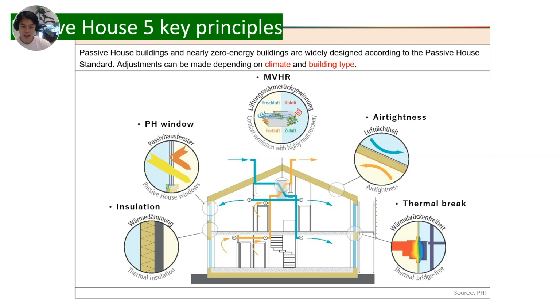That's why mechanical ventilation systems incorporate heat recovery features, namely HRV, heat recovery ventilation, and ERV, energy recovery ventilation. In high humidity environments, ERV systems are necessary because they regulate humidity, providing a form of passive dehumidification. Note that this is not the same as a conventional dehumidifier. However, in extremely humid conditions, a dehumidifier may still be needed.